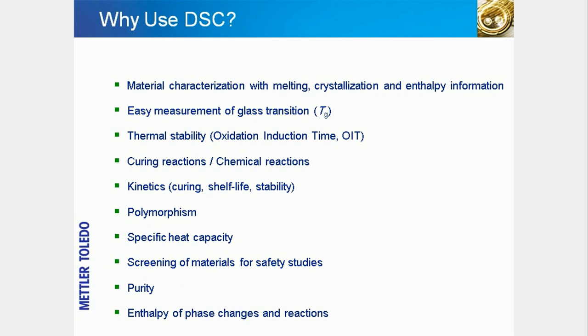DSC has a very wide application range and the method can provide a great deal of information. One of the most important applications is the characterization of samples according to their material-specific properties, such as melting, crystallization, and change in enthalpy on heating. The glass transition temperature can also be used to characterize materials, and this transition is an important physical property in its own right. Thermal stability as defined by the oxidation induction time or the decomposition temperature is an important quality control parameter.